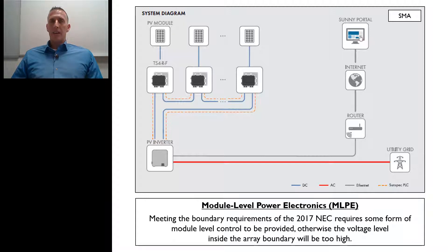This is where we're looking at possibly the higher increased use of AC modules, or it could be microinverters, or it could be the DC to DC converters. And so just keep in mind that meeting the boundary requirements of the 2017 NEC is going to require some form of module level control to be provided. Otherwise, the voltage levels inside the array boundary will just be too high.